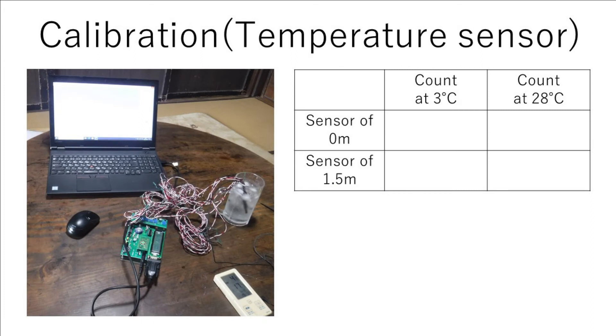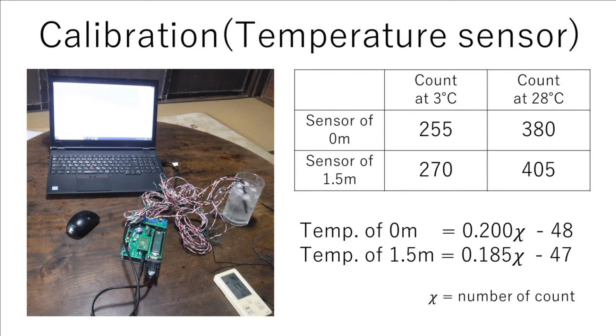Calibration is needed to get the calculation formula. The data count of the temperature sensors were confirmed at two temperatures. Since the outputs of each temperature sensor are different, the calculation formula is required separately.